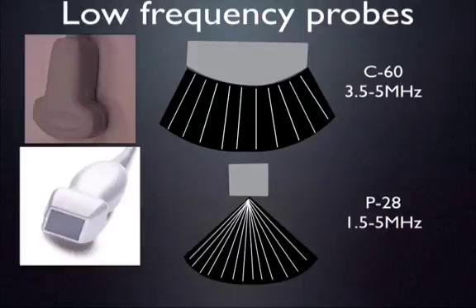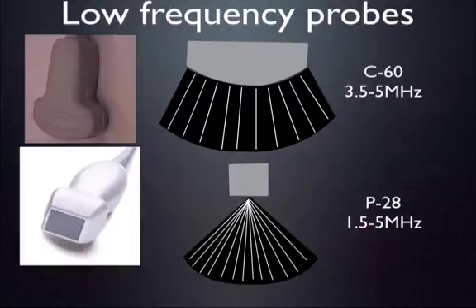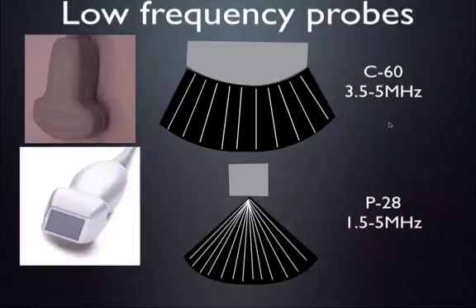Low frequency probes allow you to look deeper, but the resolution is usually a bit worse. The probe commonly called the curved linear probe — some call it the abdominal probe or the C60 probe because it's 60 millimeters along the scan face — produces sound waves in a curved fashion. It is a 3.5 to 5 megahertz probe, most commonly used for the abdomen.